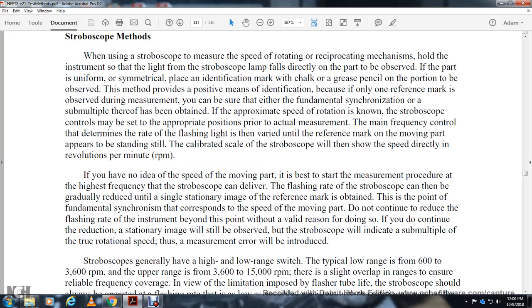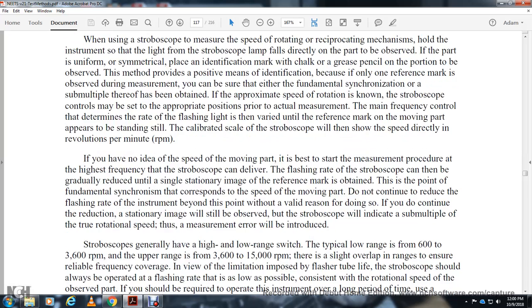If you have no idea what the speed of the moving part is, the best procedure is to start the measurement with the highest frequency the strobe can deliver. The flashing rate of the stroboscope can then be gradually reduced until a single stationary image appears. The reference mark obtained at this point of fundamental synchronism corresponds with the speed of the moving part. Do not continue to reduce the flashing rate of the instrument, as there is no valid reason for doing so. If you do continue to reduce it, a stationary image will still be observed, but the stroboscope will indicate a submultiple of the true rotational speed, and an error will be introduced.